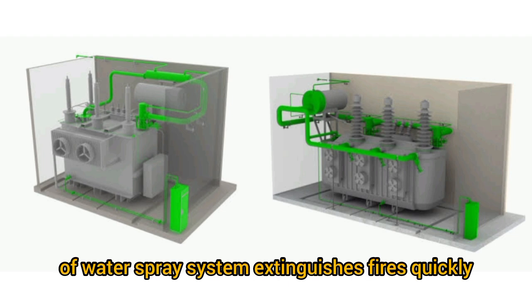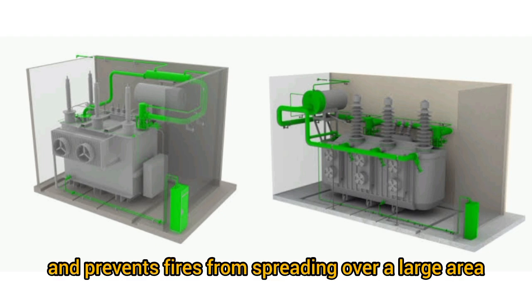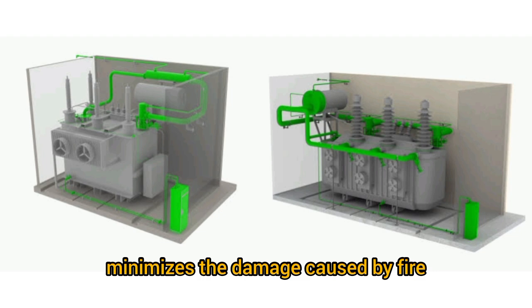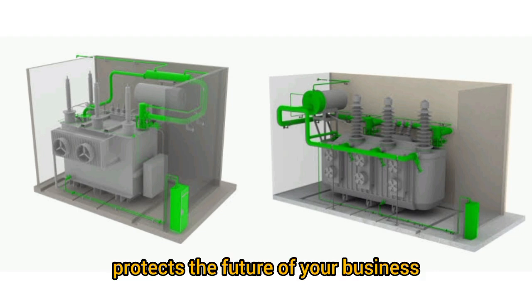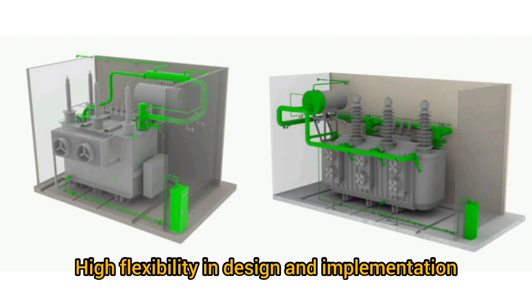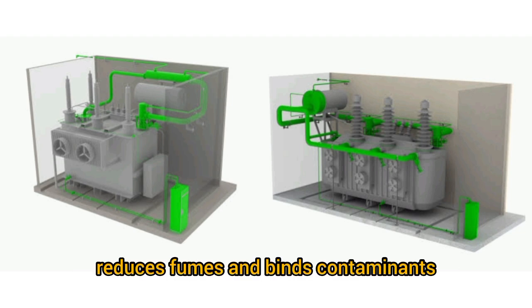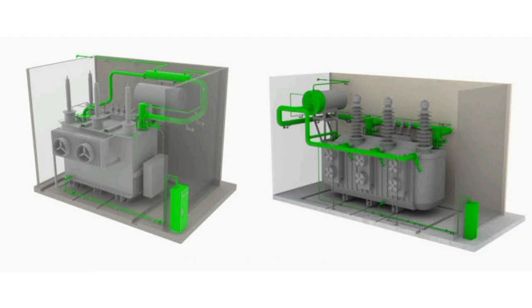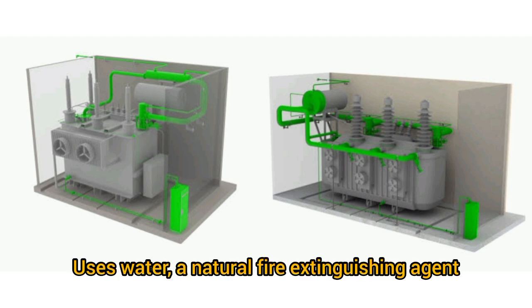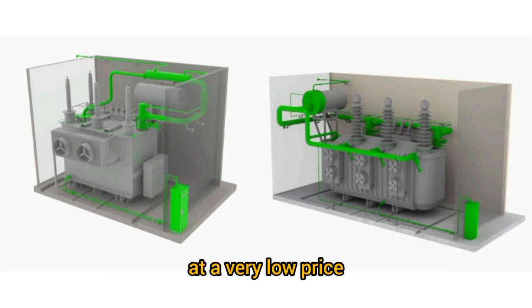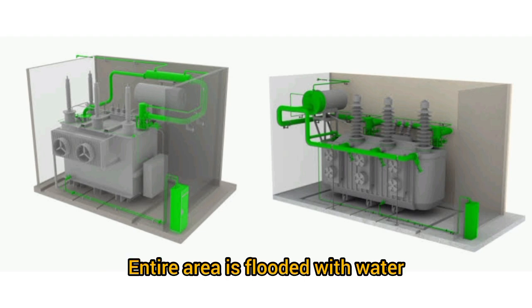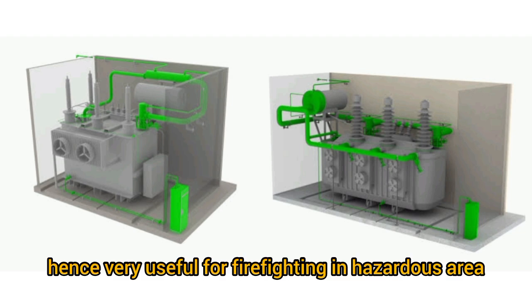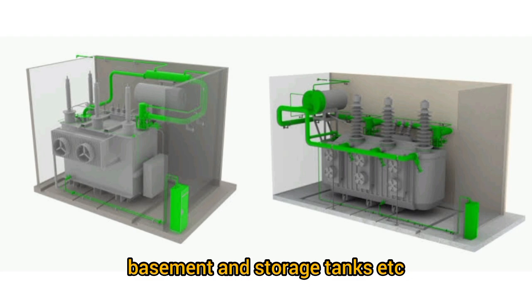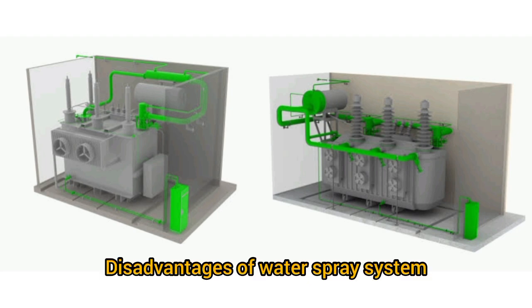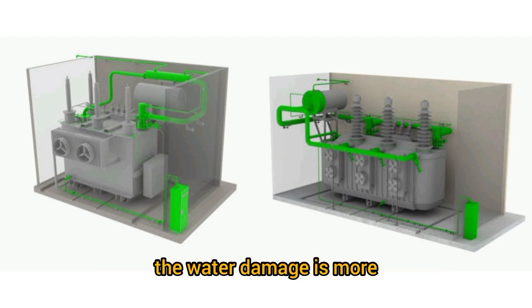Advantages of water spray system: extinguishes fires quickly and prevents fires from spreading over a large area, minimizes the damage caused by fire and reduces downtimes, protects the future of your business. High flexibility in design and implementation, reduces fumes and binds contaminants, allows large open areas and thus a more flexible use of the premises. Uses water, a natural fire extinguishing agent that is available in unlimited quantities at a very low price. The entire area is flooded with water, hence very useful for firefighting in hazardous areas, basements and storage tanks, etc. Disadvantages of water spray system: as the entire system gets flooded with water, the water damage is more.